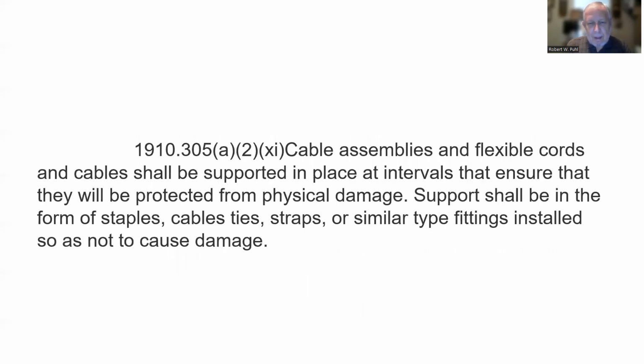Extension cords, basically. Cable assemblies and flexible cords and cables shall be supported in place at intervals that ensure that they will be protected from physical damage. Support shall be in the form of staples, cable ties, straps, or similar type fittings installed so as not to cause damage.